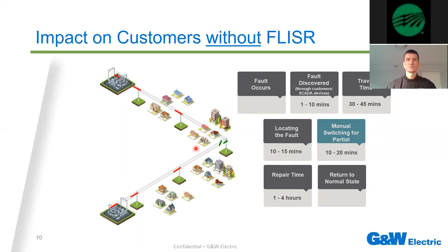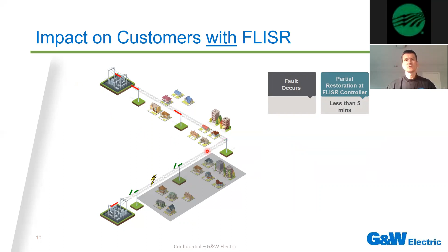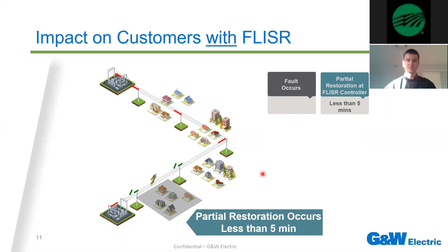So now let's look at the same example here for customers with FLISR, right? Same system setup, same fault occurs, and now we are doing a switching operation that is essentially doing the partial restoration in less than 5 minutes. Before that, we had to deploy a crew, isolate the fault, and do the manual switching operation of closing the tie point and closing the substation breaker back in to supply power to this one section here that is not affected by the fault. And it took a good amount of time to do so, because it was a manual operation and you actually needed to deploy a crew. Now with automatic operation, the goal, and that's defined in IEEE standards, is to do that partial restoration in less than 5 minutes.